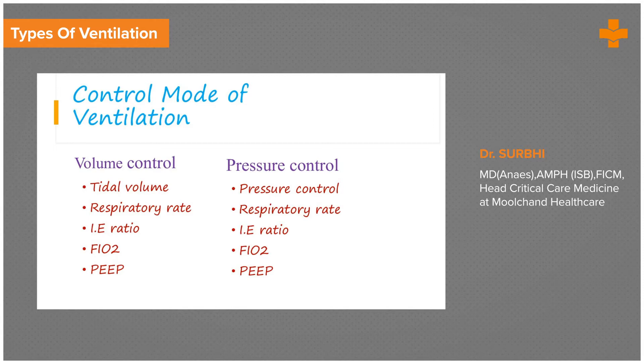In Pressure Control, we set the pressure control and at the same time we keep monitoring how much tidal volume the patient is generating. In Volume Control, when we set the tidal volume we should keep an eye on the airway pressures. In Pressure Control, we set the pressure and look for how much tidal volume is generated; accordingly we can set the respiratory rate to reach a targeted minute volume, I:E ratio, and FiO2.